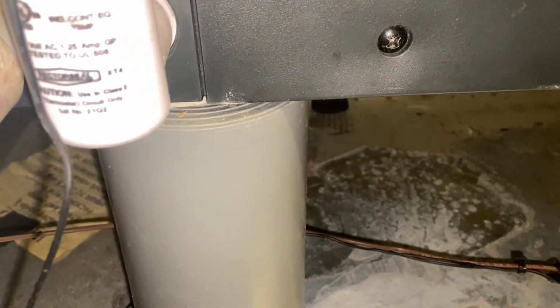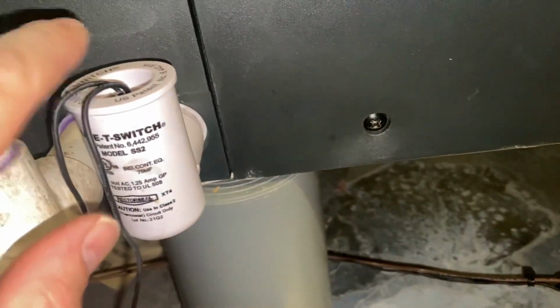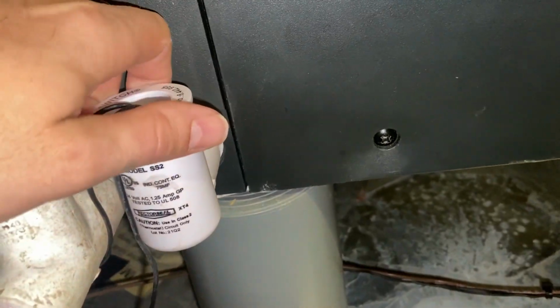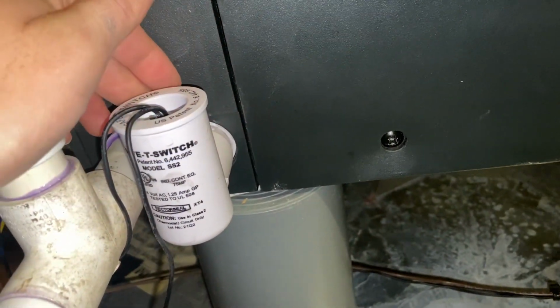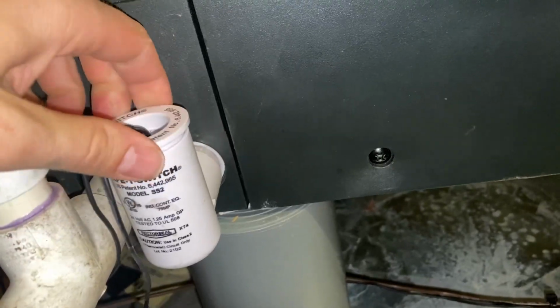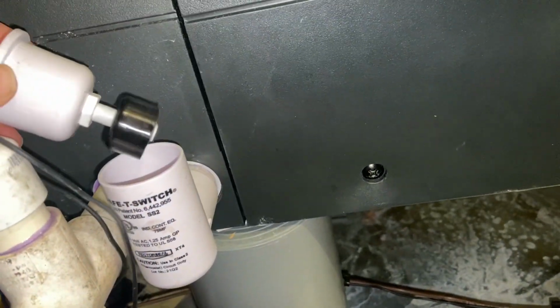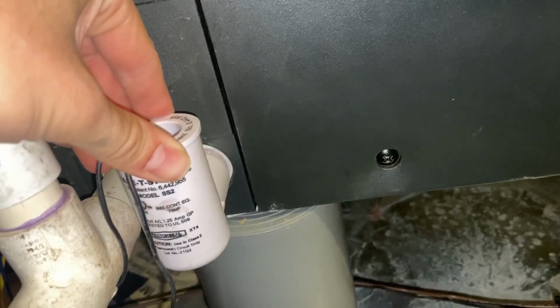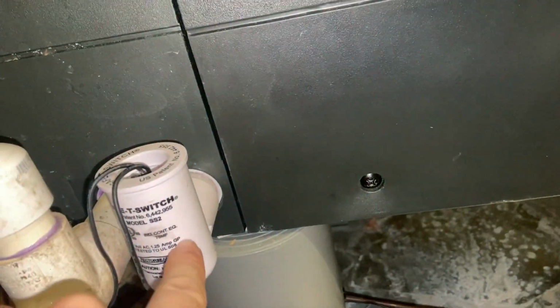I tested them independently and found that the problem was with this switch right here. I guess what happened was somehow I got a condensate backup that was tripping the switch, and this thing just pops out. That's how the system works — as this fills up, it trips the switch.